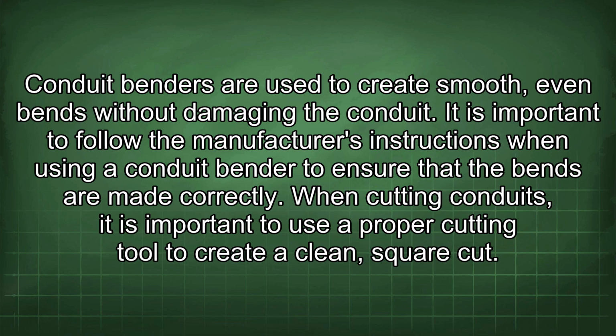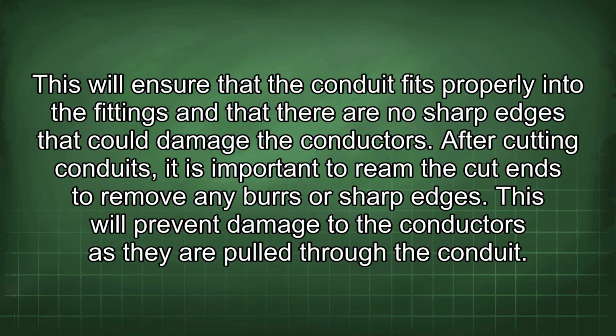It is important to follow the manufacturer's instructions when using a conduit bender to ensure that the bends are made correctly. When cutting conduits, it is important to use the proper cutting tool to create a clean, square cut. This will ensure that the conduit fits properly into the fittings and that there are no sharp edges that could damage the conductors. After cutting conduits, it is important to ream the cut ends to remove any burrs or sharp edges. This will prevent damage to the conductors as they are pulled through the conduit.